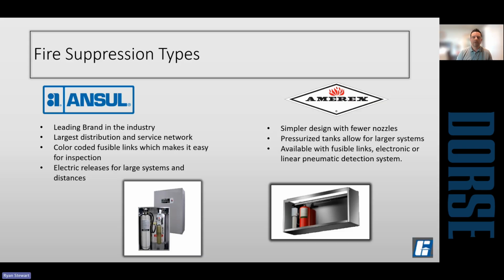For the most part, detection for these systems is mechanical. We have started to see some manufacturers push electronic detection into it, where you'll have electronic fire stat, electronic pull stations. They're great systems. The one thing that I think needs more support is traditionally the fire subs have been plumbers. They hook up the pipes, they're able to run the detection line, do the pull station. When you add in the electric aspect, it basically pulls the part that makes the system work out of their scope.